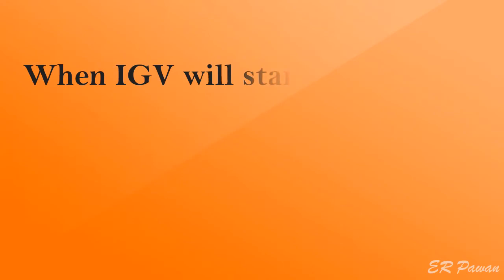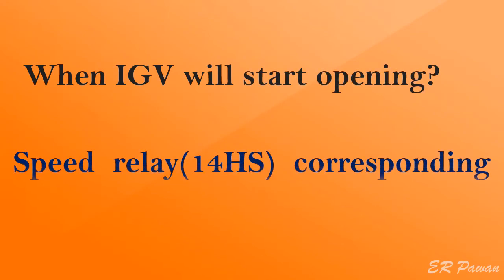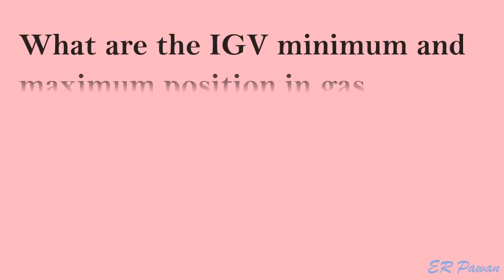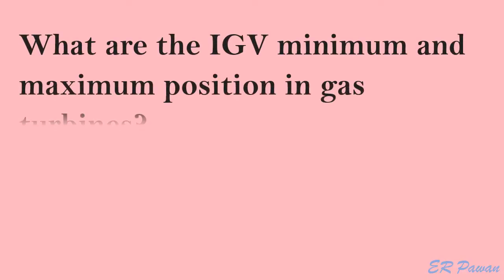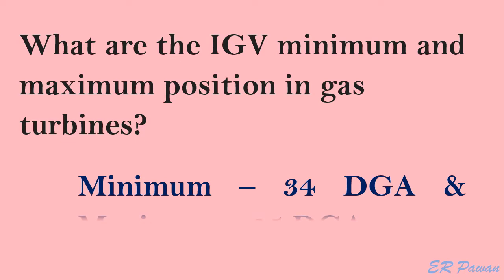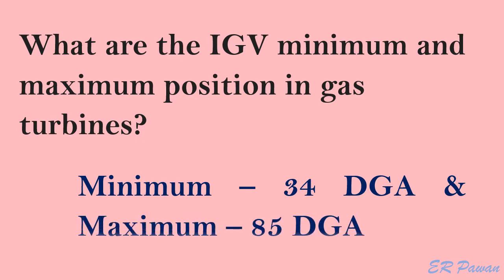When will the IGV (Inlet Guide Vanes) start opening? Speed relay 14HS corresponding to 95% speed. What are the IGV minimum and maximum positions in gas turbines? Minimum 34 degrees and maximum 85 degrees.